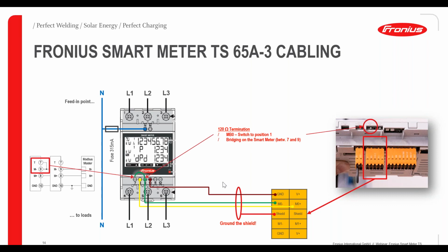One other important thing, because it's a serial Modbus connection, we need to terminate the loop at the end of the loop, at both ends of the loop. On the smart meter itself, the 120 ohm termination resistor is already integrated. The only thing you need to do is bridge pin number 7 and 8 here. This way you have activated the 120 ohm termination.